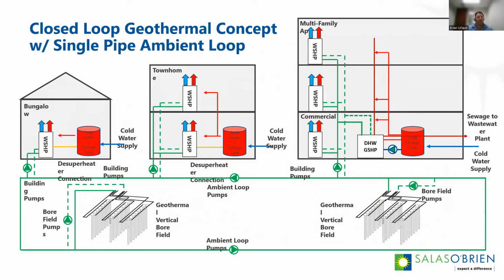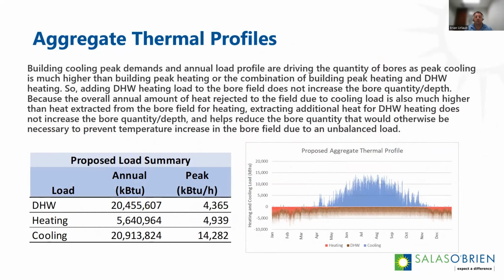What we came up with is another single pipe ambient loop with distributed ground loops around the site to interconnect everything. We're also taking in all the domestic hot water load, since there's a lot of diversity, especially with the multifamily buildings and hotel, letting us capture more diversity in that domestic hot water. We can also recapture energy through sewage heat recovery and inject that back into the ambient loop as another energy source. These were critical things to look at in our aggregate profile, to determine how much energy we need, where we need it, and what diversity we can take into account.